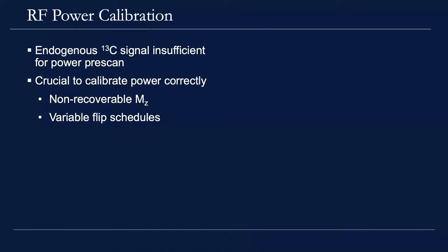I'm alluding to B1 mapping, yeah. So you can do it with a carbon phantom, right, by looking at the spectra and looking for the signal null and then estimating the flip angle, the power, from there. But if you wanted to get a B1 plus map, how could you do it with hyperpolarized spins where you can't really do a double angle approach, and magnitude-based approaches don't really work because of the changing magnetization?